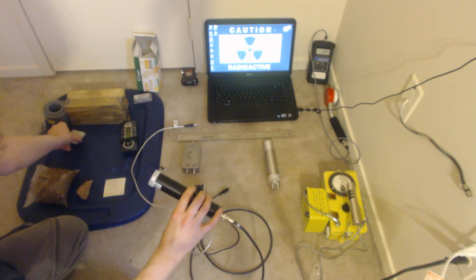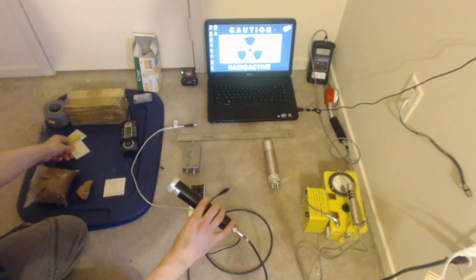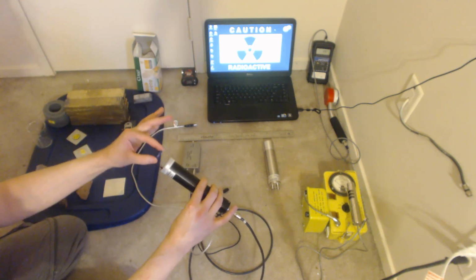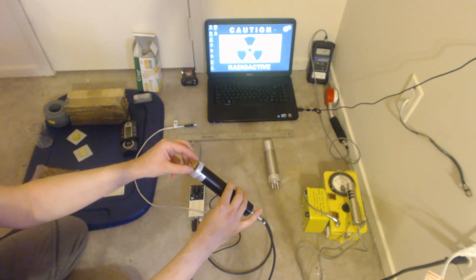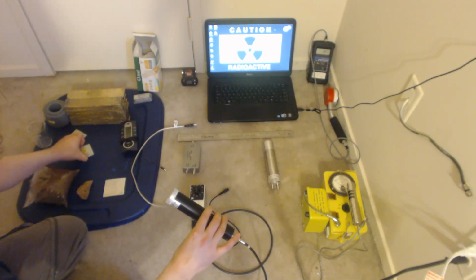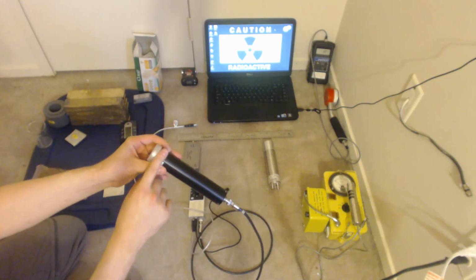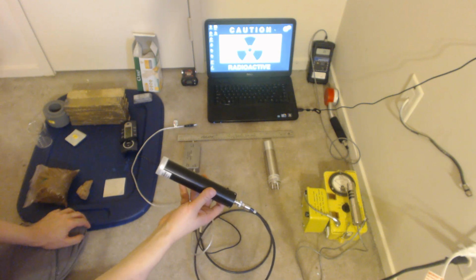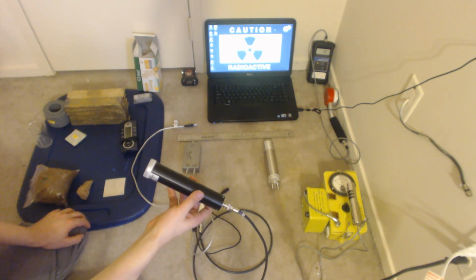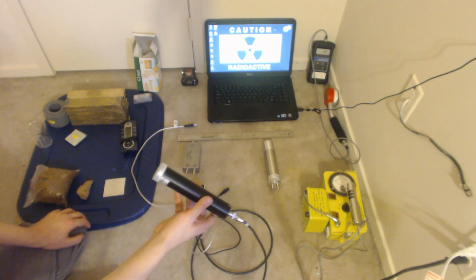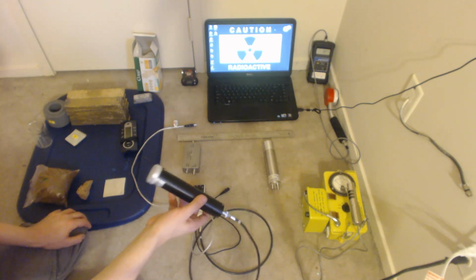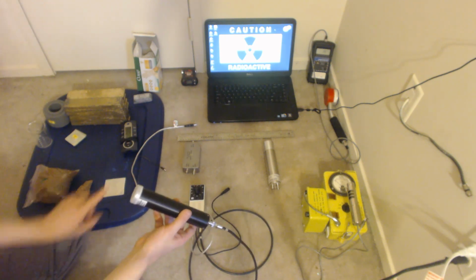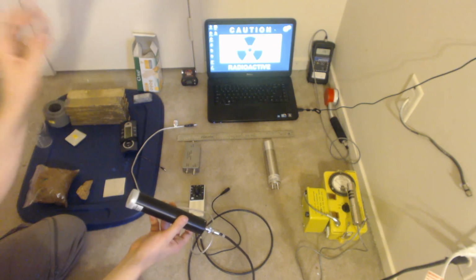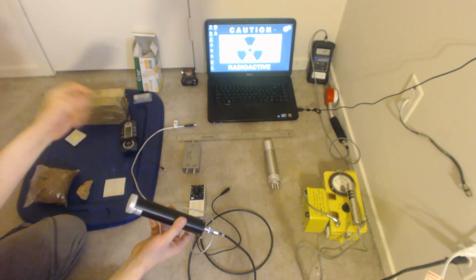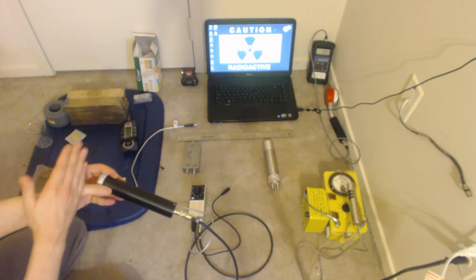Here's what happens. When something radioactive, like this cesium-137 sample right here, emits gamma rays that hit the crystal inside of here, the gamma rays will produce flashes of light. The number of photons produced is proportionate to the amount of energy of the gamma ray that hit it. High energy gamma ray, lots and lots of photons. Low energy gamma ray, a couple of photons.